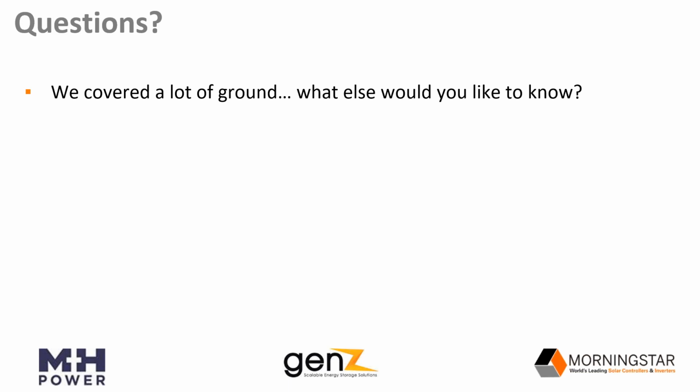Yep, again, let me answer that question. So the biggest capacity we've got in a 48-volt is the 3 kWh, or it's equivalent to a 60 amp hour. In terms of limitation, in terms of daisy chaining them in parallel, it's virtually unlimited. The only limitation that you have to consider is your bus bar, or your common bus that you'll have to connect to the power system, because each battery delivers up to 60 amp, and 10 batteries that's 600, 20 batteries that's 1200 amps. So that's what you have to factor in, but virtually there is no limitation. All right, very good, no limitation.